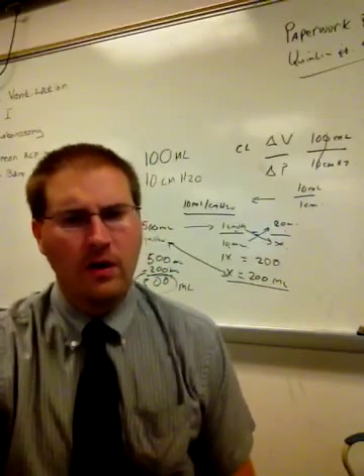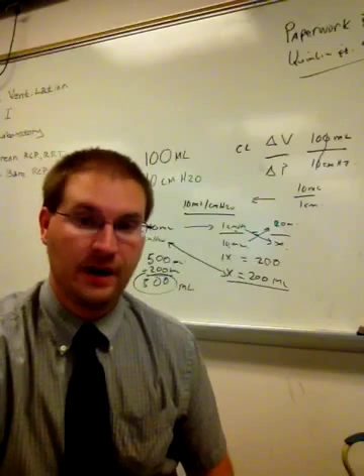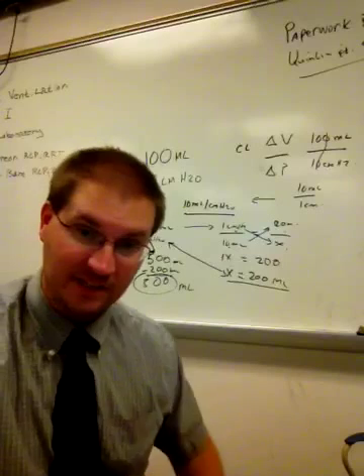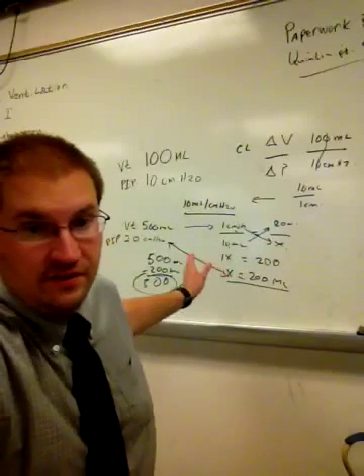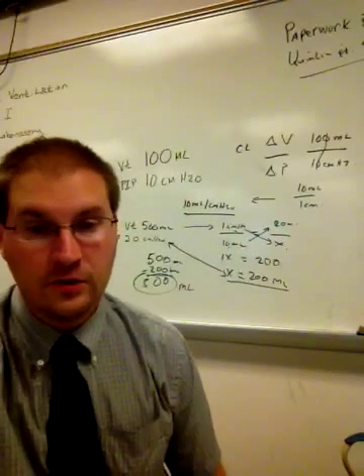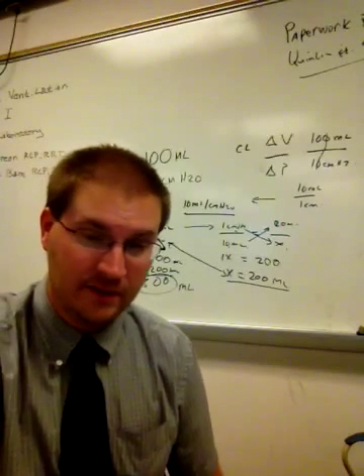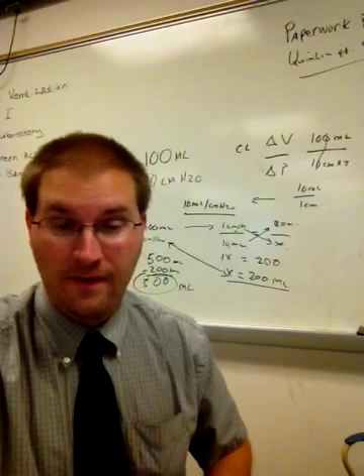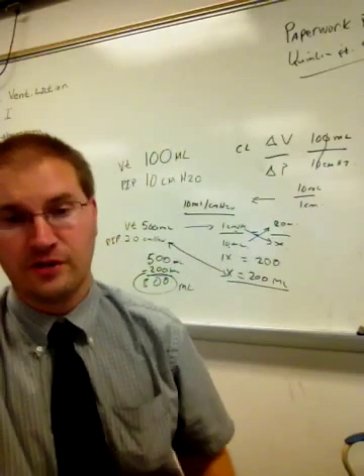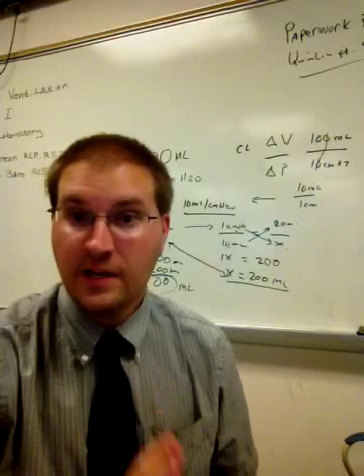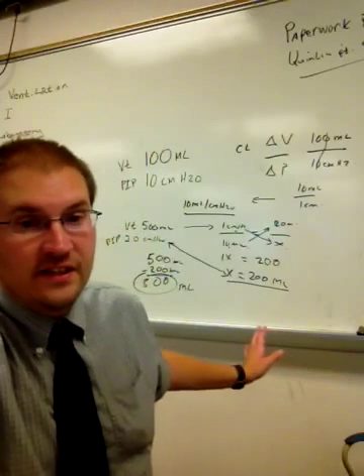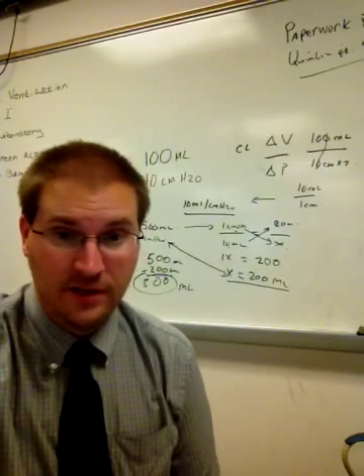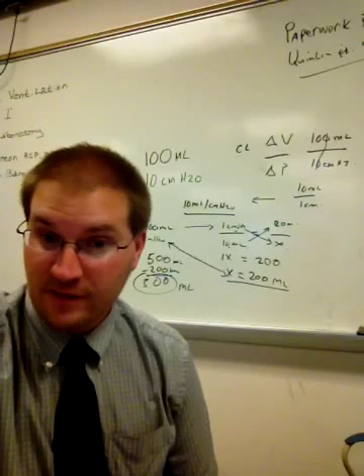Now, I want to be very clear, we don't do this manual calculation on every patient, every time we hook somebody to a ventilator. Most of the modern microprocessor ventilators incorporate this into that SST, and that's actually why it is so important to perform that SST, because the ventilator will then know how much volume it will lose to circuit compliance, basically to mechanical dead space. Now, this is not physiological dead space, that's something a little different. That's in the airway itself. That is air that is not being in the process of gas exchange, in the conducting airways, basically. Different concept than the concept we're talking about here. Again, this is something that you would do on an older style ventilator, where they don't have that SST option, and you actually have to manually calculate volume loss, the circuit compliance. It's not something we do commonly, but it definitely is something that they put on tests.